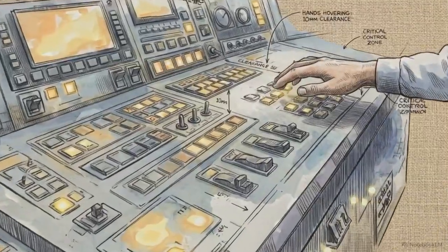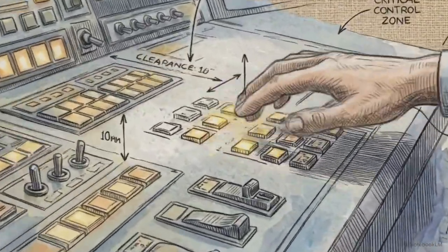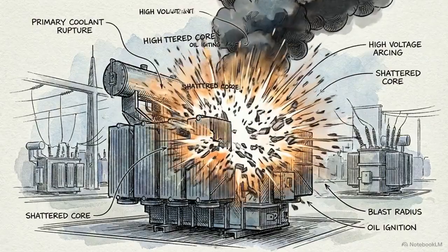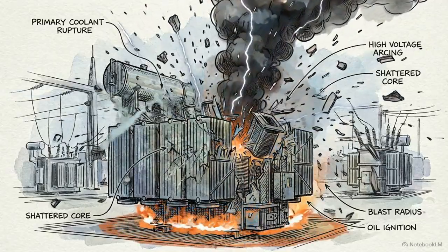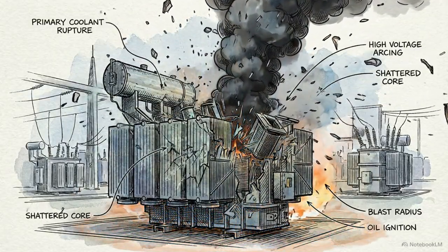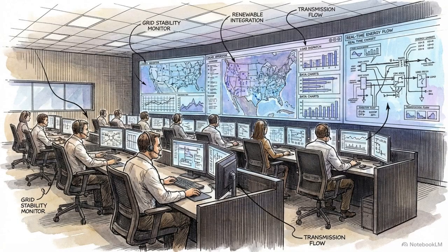A 40 kilovolt overvoltage at the end of the line is not the result of an operator making a mistake. It is a mathematical inevitability dictated by the geometry of the wire and the physics of alternating current. This piece of heavy hardware is a 345 kilovolt three-phase shunt reactor. Shunt reactors act as heavy-duty anti-capacitors. By engaging massive magnetic coils, they absorb the excess reactive power and directly counteract the line's charging current. Without these massive inductive anchors permanently stationed at receiving terminals, long-distance power lines would eventually generate enough internal pressure to physically destroy themselves. Grid operators wage a daily battle against the line's physical nature.